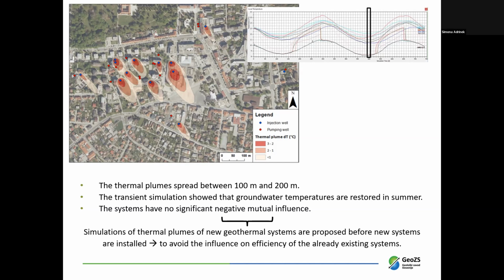The transient simulations showed that groundwater temperatures are restored in summer when the systems are not in operation. We can conclude that at the moment there is no significant negative mutual interference between the systems, although thermal plumes merge at certain locations or reach the catchment area of another pumping well. But this change is less than 1 degree on average, so it does not affect the overall efficiency of the systems.